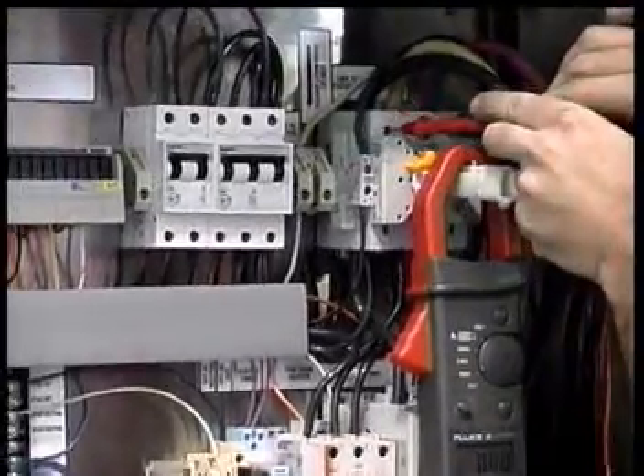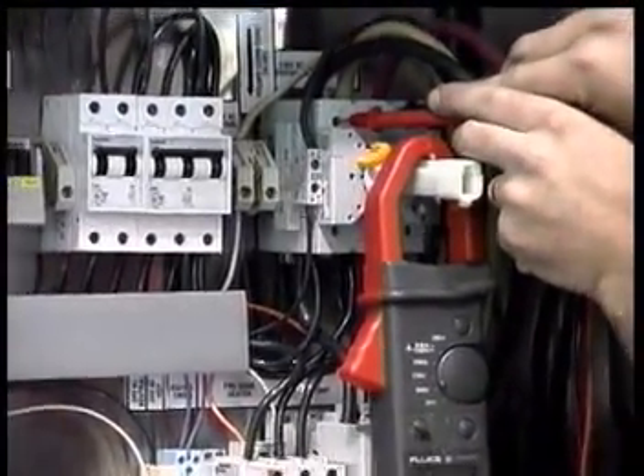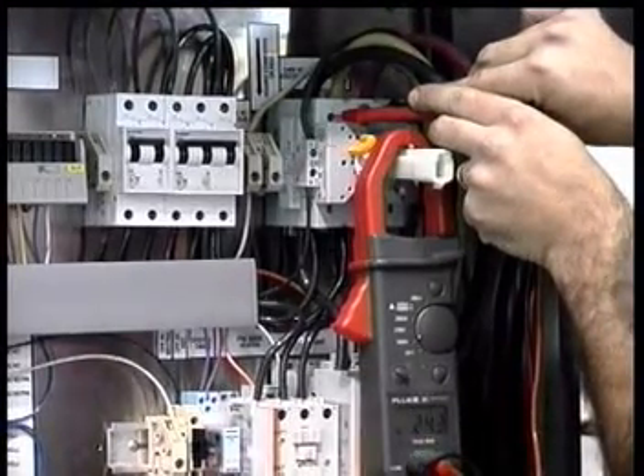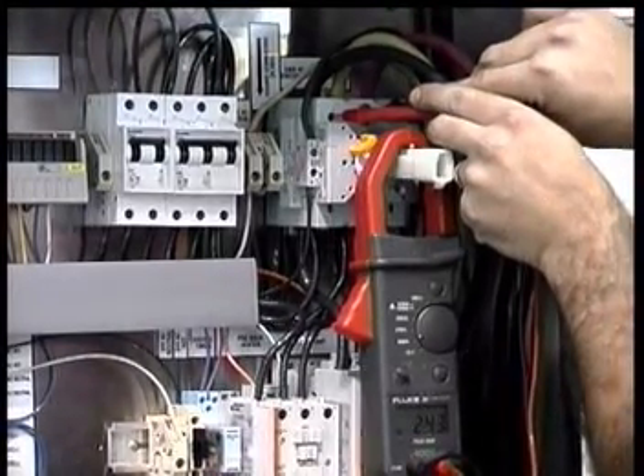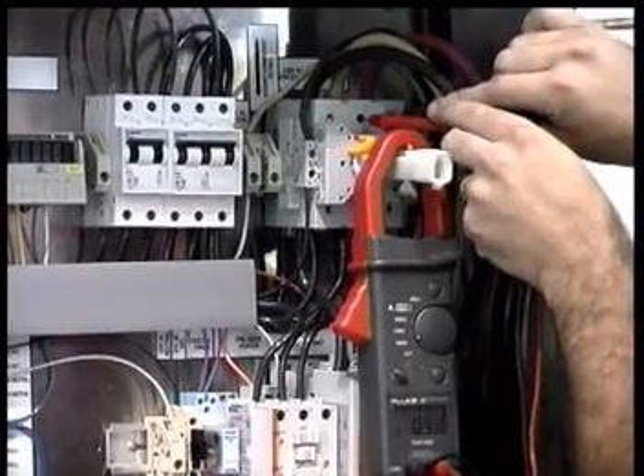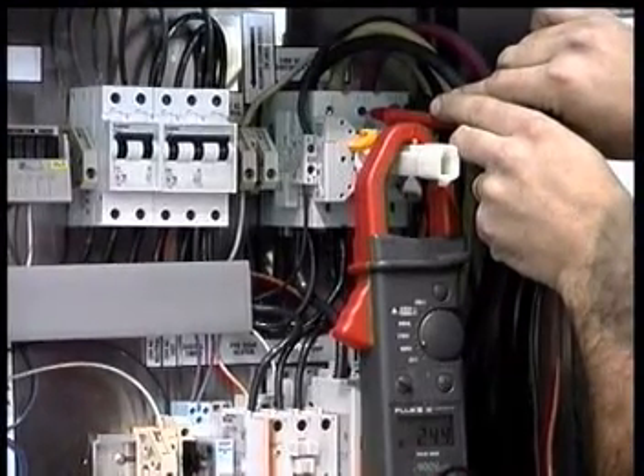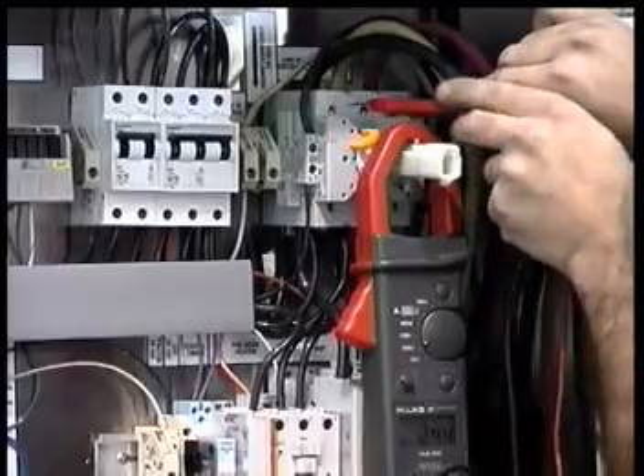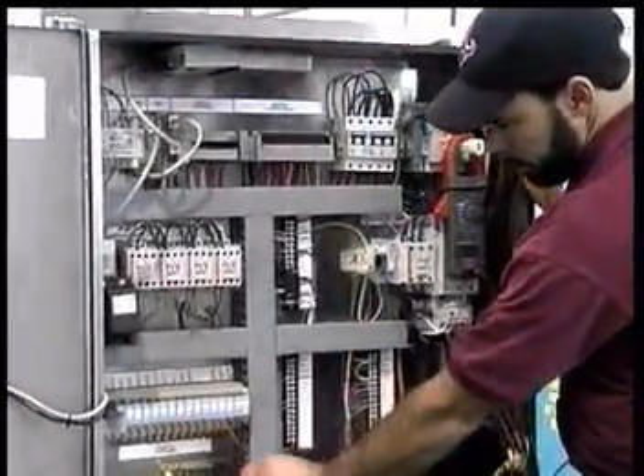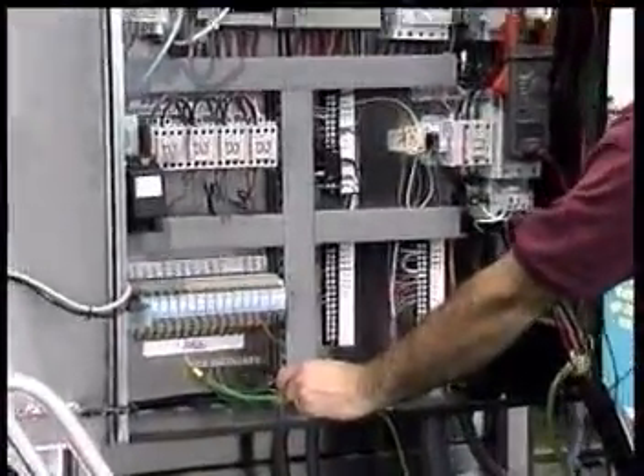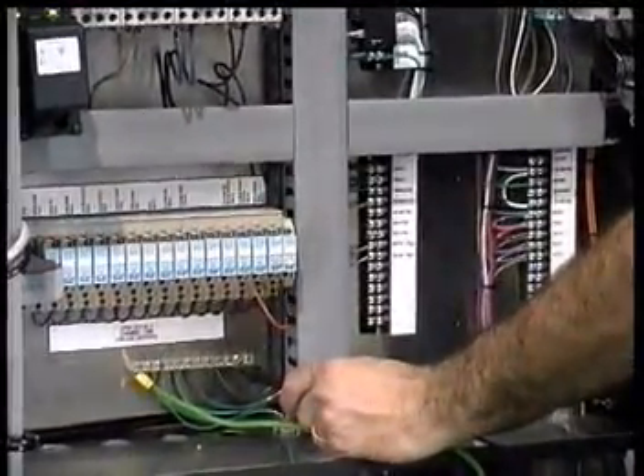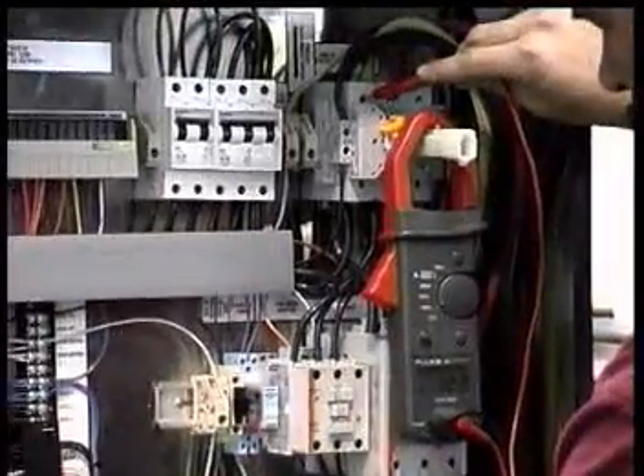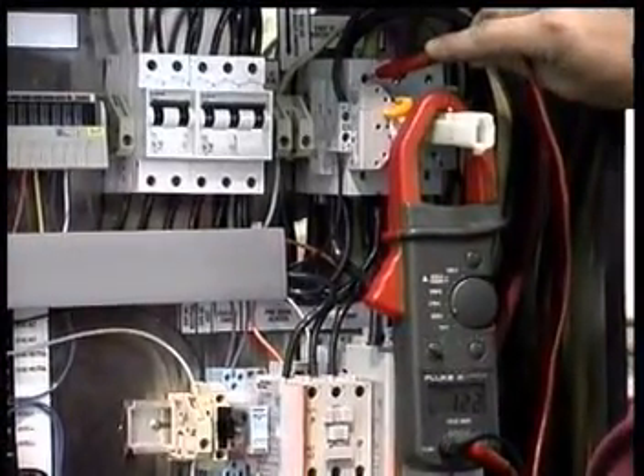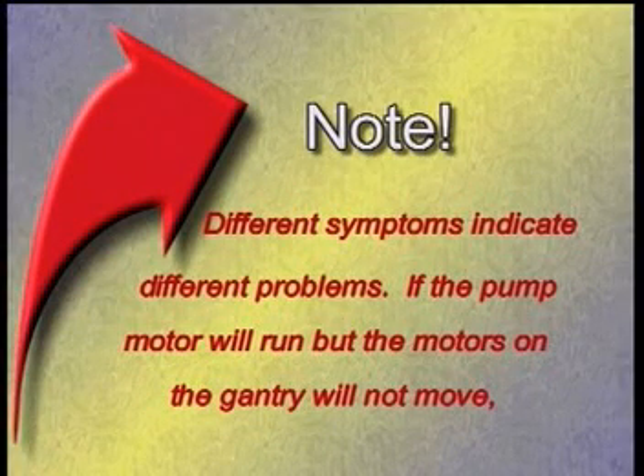Next, check for proper voltage at the top side of the main disconnect on the control panel. Test voltage between terminals L1 and L2, then L2 and L3, and last L1 and L3. Voltage should be between 205 and 240. Then go from each leg to ground. Voltage there should be 110 to 120 volts. In some cases, due to the type of three-phase power available in your area, one of these legs may read higher than 110 volts. Different symptoms indicate different problems.